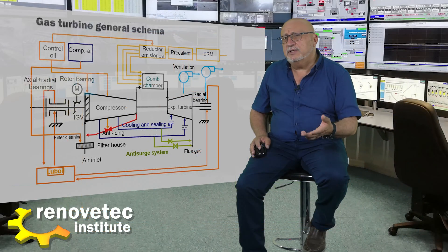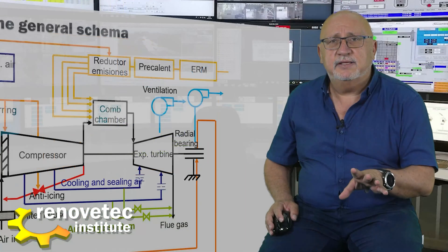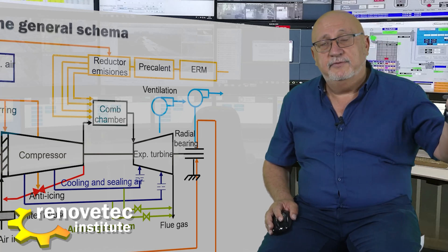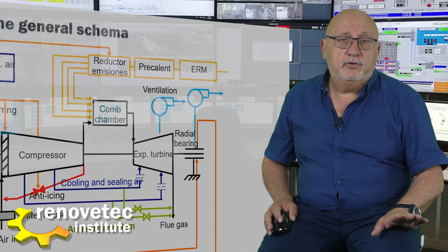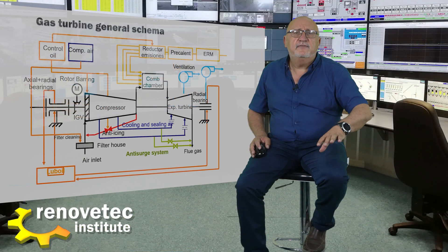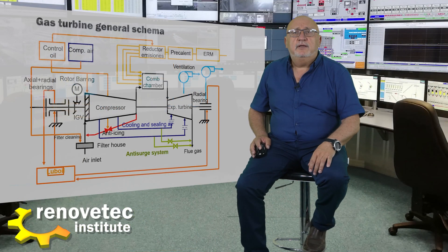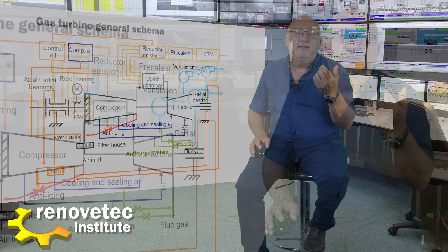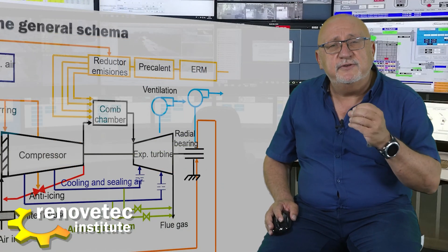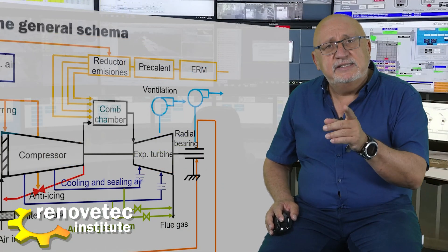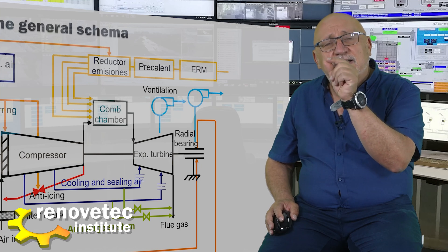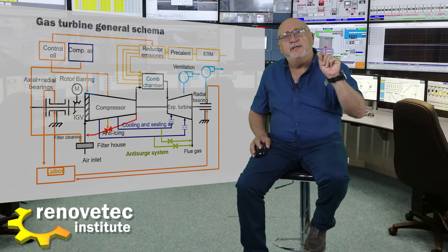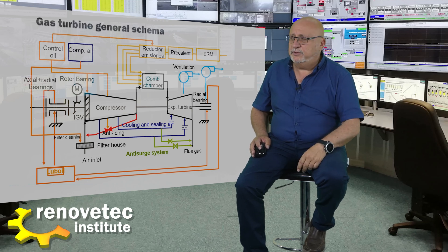The last element is the anti-icing system. Sometimes when the ambient air is very cold — less than five degrees — the water contained in the air can freeze at the first compressor stage. To avoid this, there is a system that routes a small part of the hot air from the outlet of the compressor back to the inlet of the compressor.